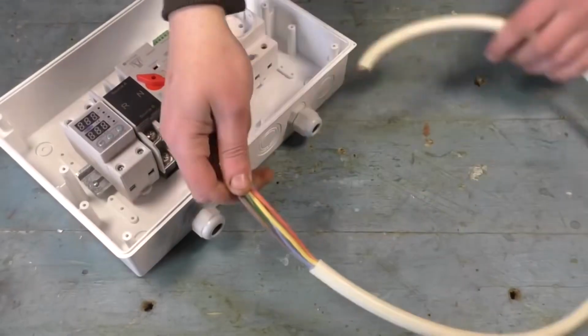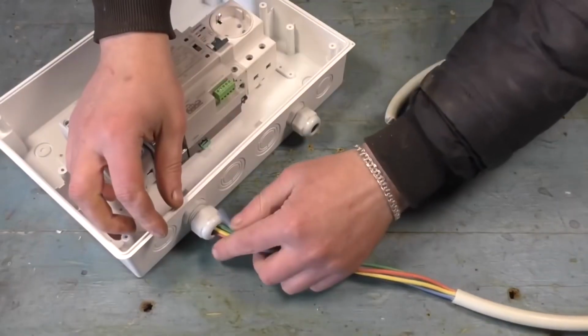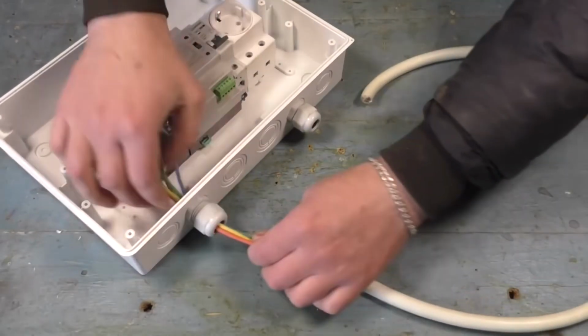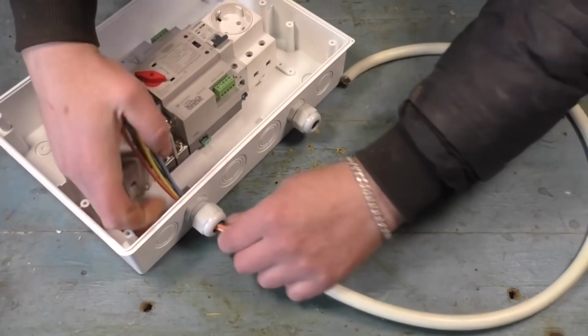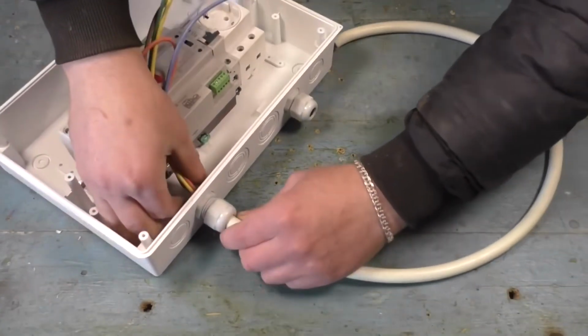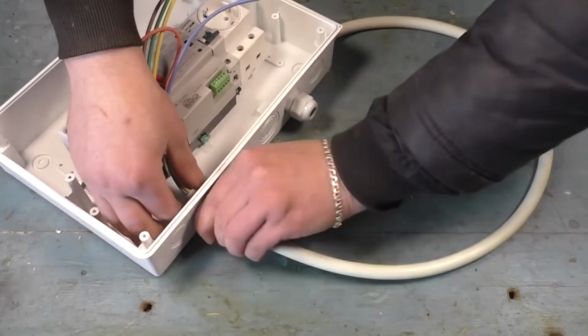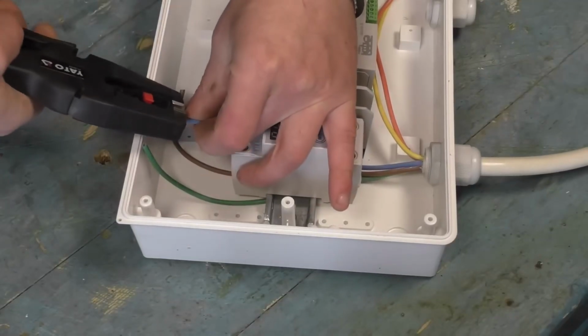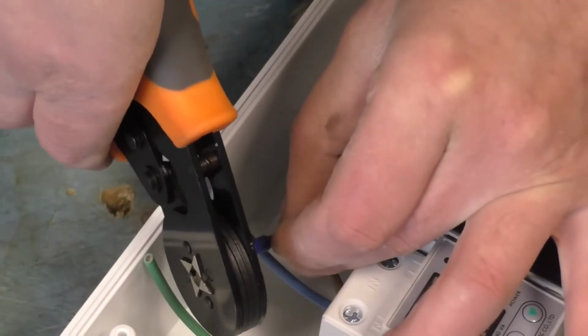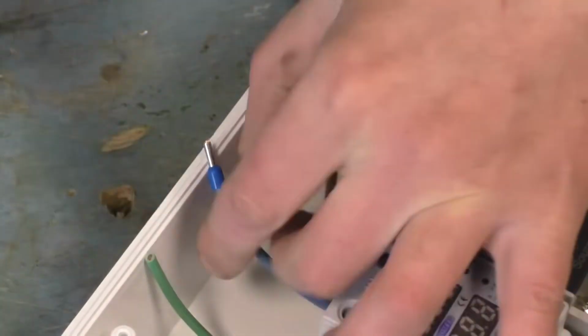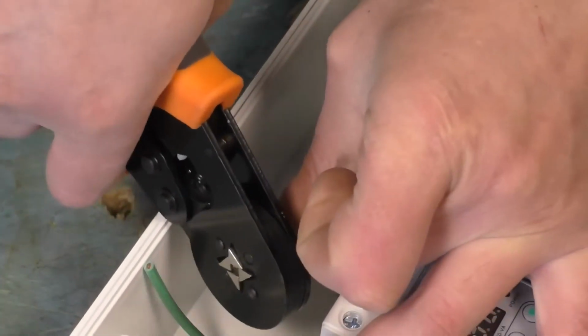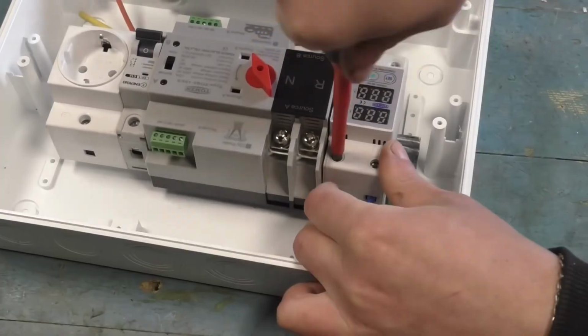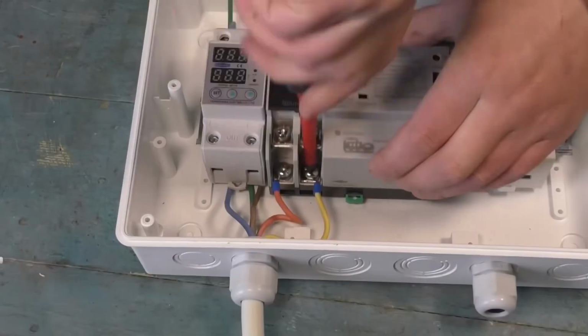We insert a 5-core cable with a cross section of 2.5 square millimeters into the first input. With this cable, the device will be connected to the panel where the meter is installed. We strip the insulation, then crimp each core with wire ferrules. Next, we connect any 2 cores to the input of the voltage relay, leave 1 core for grounding, and connect the remaining 2 to the output.